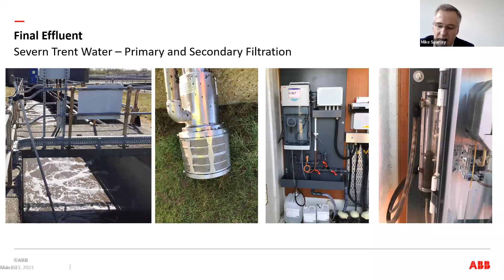What we tended to do was add a secondary filter, a manual, easy-clean metal mesh system. You can get these from about 50 micron up to 400 micron. Typically with a primary and secondary system, we'd go up to about 300 micron on the primary, then bring it down to about 100 micron on the secondary. You can see it installed here, it's just unscrewing it, giving it a quick wash, and putting it back in.